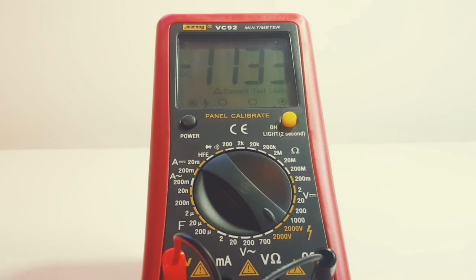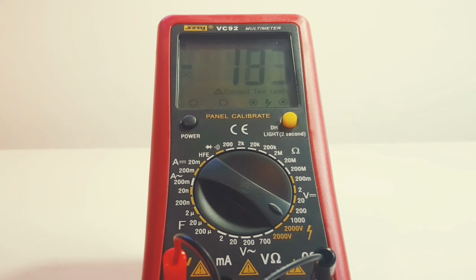But it is certainly capable of getting that far. Now if I bring it down to 1000 volts, let's see if we have an audible warning of any sort - and it just goes OL. So no audible alarm in the high voltage mode if we go over.